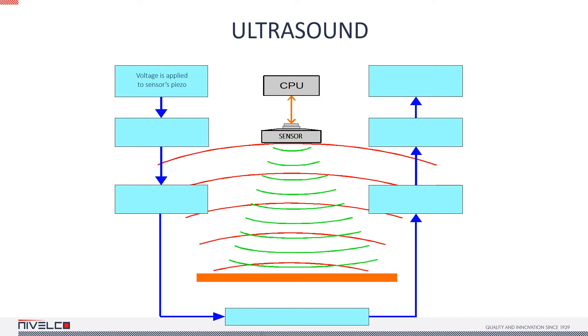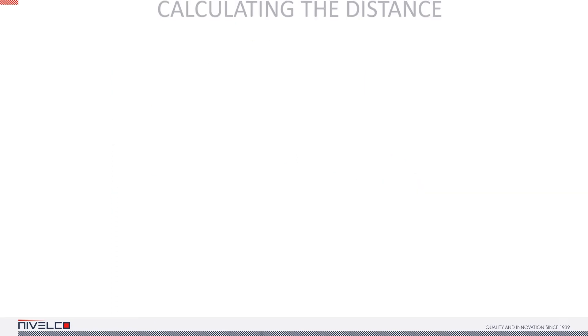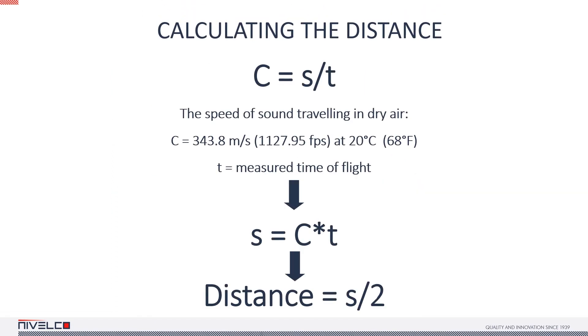Inside the device, voltage is applied to the sensor's piezo. The piezo starts to resonate and creates an ultrasonic burst which travels towards the target through the air. Then it's reflected from the surface of the target and travels back to the sensor. It hits the piezo and makes it resonate which creates a voltage pulse and the pulse is received by the processor which converts it into a signal. Once we know the travel time, it's easy to calculate the distance using C, the speed of sound in dry air at 20 degrees Celsius.